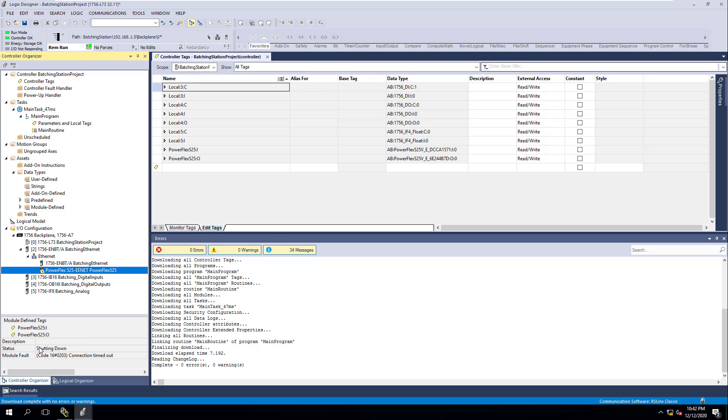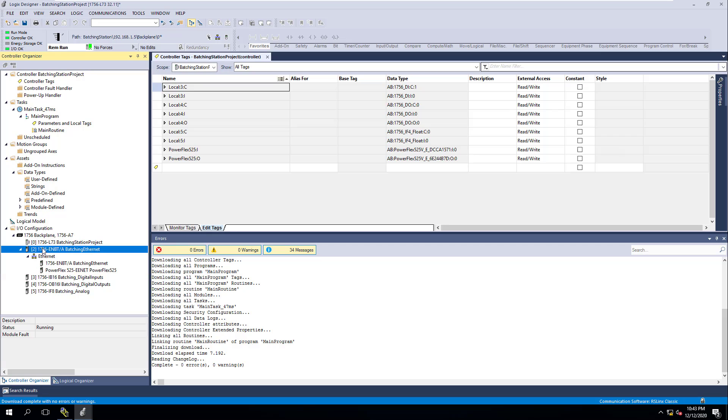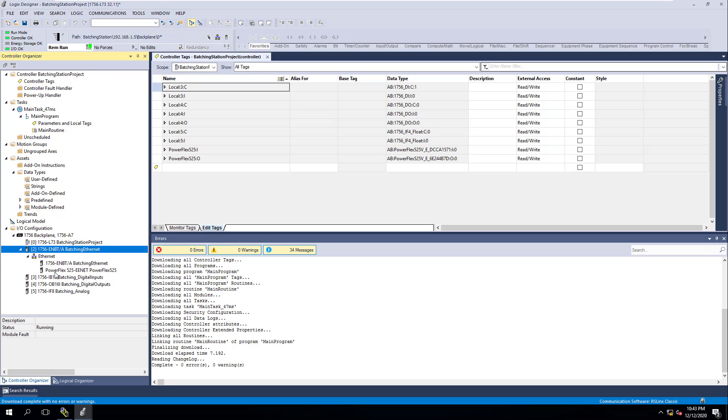If by chance I stop communicating to my PowerFlex drive, if I unplug it right now, you can see it is shutting down. So the connection status is not there, and that is what you will see. You will see a little caution symbol in the actual IO tree, and that will show you that it's not connected. In my case, I'll plug it back in real quick. It will start connecting, and then the connection will come back valid. This is what you will see if you have a connection problem or if you don't have it configured properly.